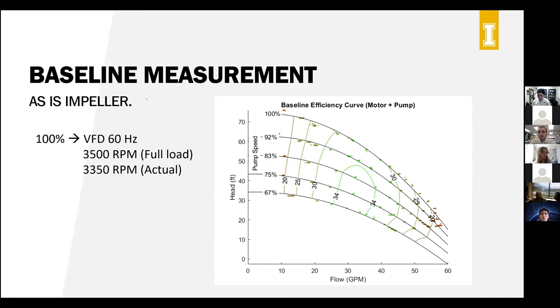And the third is that it is a low-cost motor pump assembly, and it's not designed with the best efficiency in mind. There could be some manufacturing variability, and the pump housing itself was not circular. The volute itself was more rectangular than circular. So there are a couple of things that could have gone into this pump efficiency curve. But in any case, this is the data that we're plotting. Since our most efficient speed was not 60 hertz but around 50 hertz, the subsequent comparisons were made at 50 hertz. We do have data with a similar trend, but all the comparisons are made for 50 hertz.